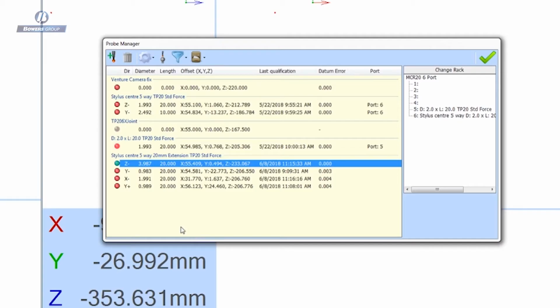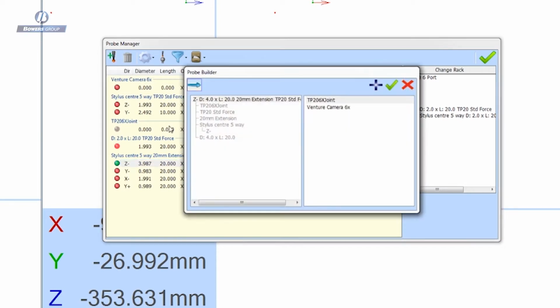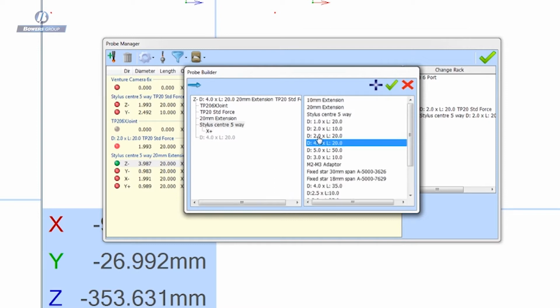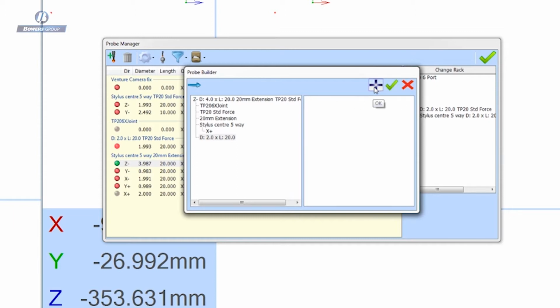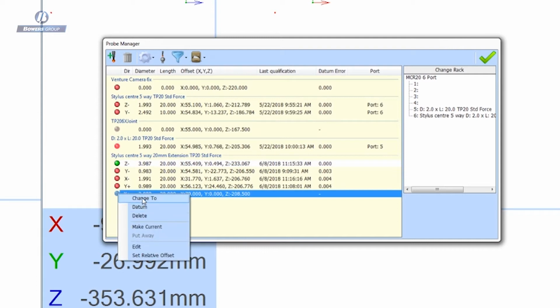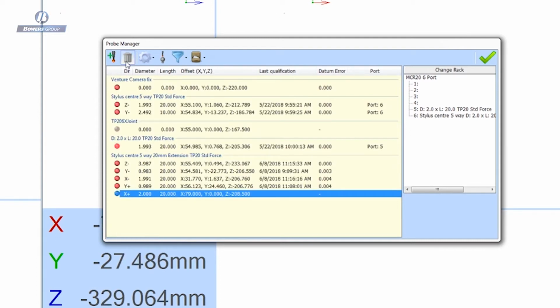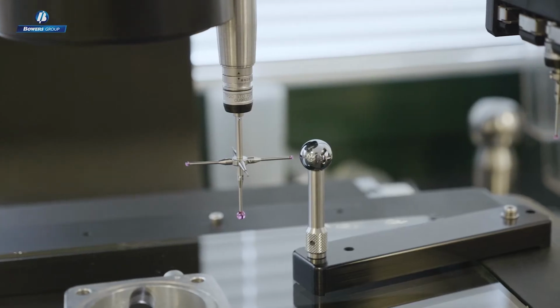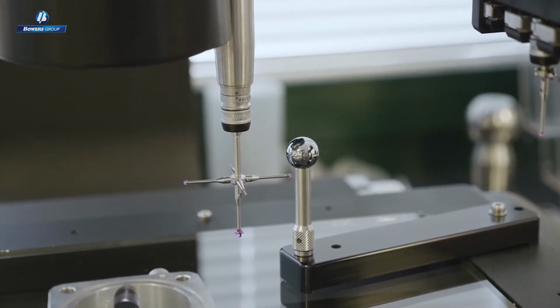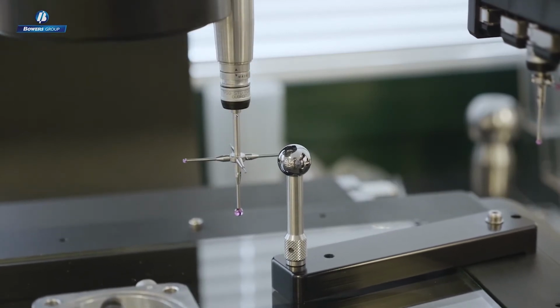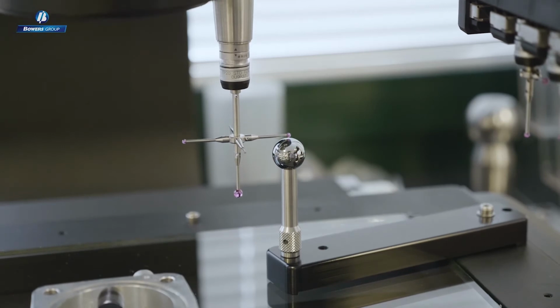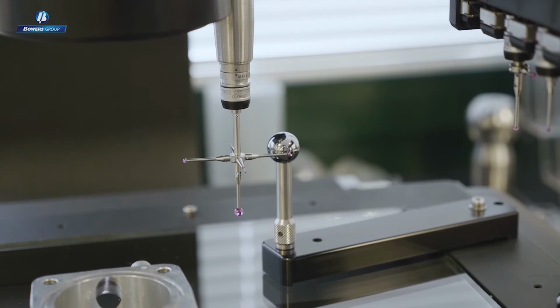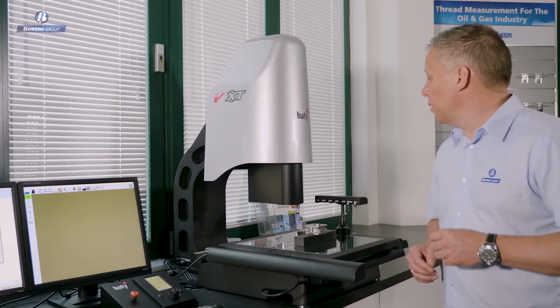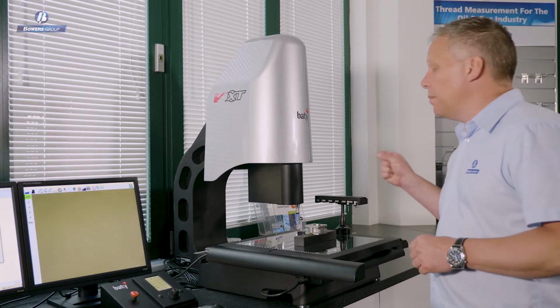I'm just going to add the final stylus to this particular probe set, and if I go up to my probe manager here, I'm just going to add the X Plus stylus. I've got a 2 by 20mm stylus mounted, so let's add that, and simply a case of making that the current stylus and then asking the machine to go and datum itself. So the machine's now driving that stylus into the reference ball.